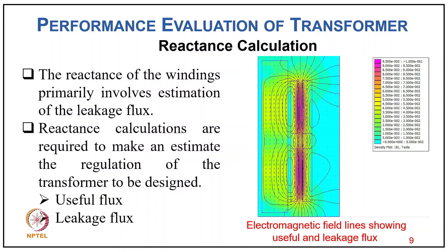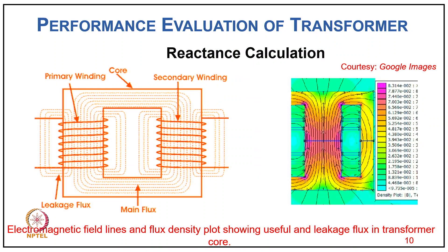For reactance calculation, the reactance of the windings primarily involves estimation of the leakage flux, and reactance calculations are required to estimate the regulation of the transformer being designed. We identify useful flux and leakage flux from electromagnetic flux line plots. The leakage flux is confined to only the particular winding limb, while the flux linking both windings is called the useful flux. This is also confirmed through FEM element analysis showing two different kinds of fluxes.